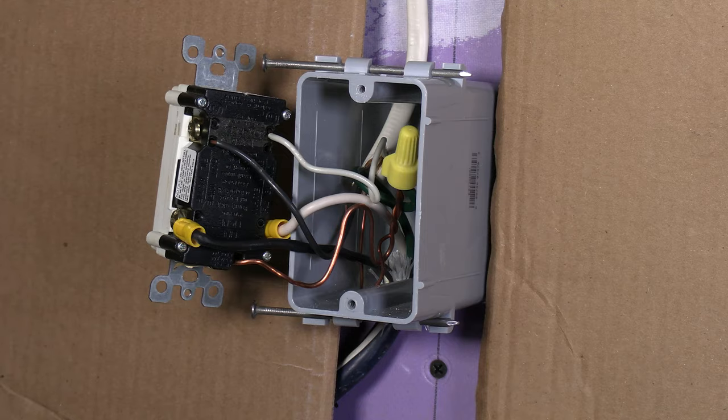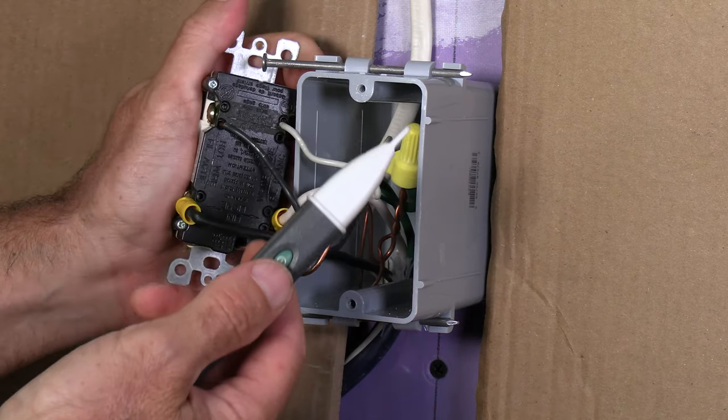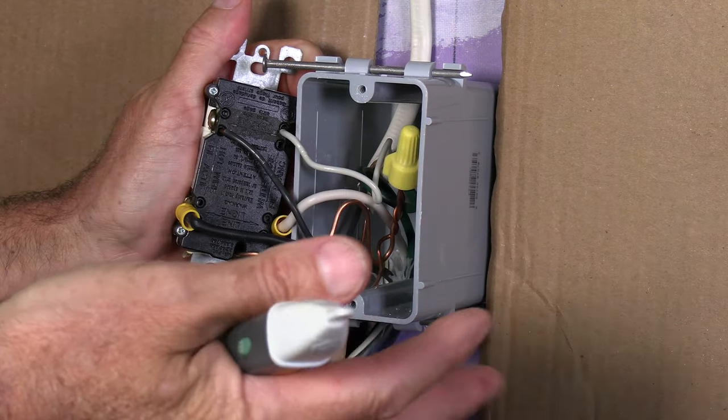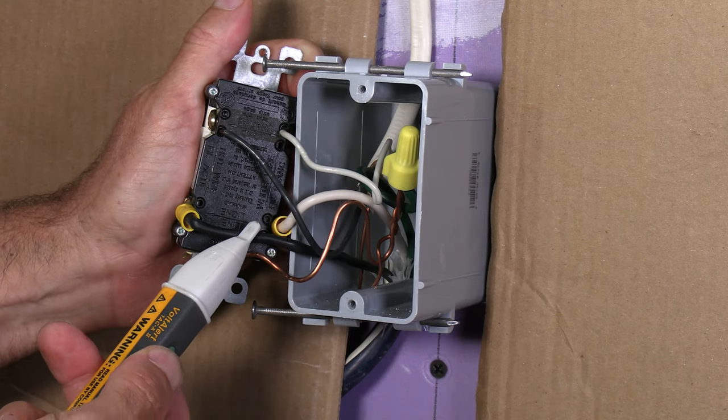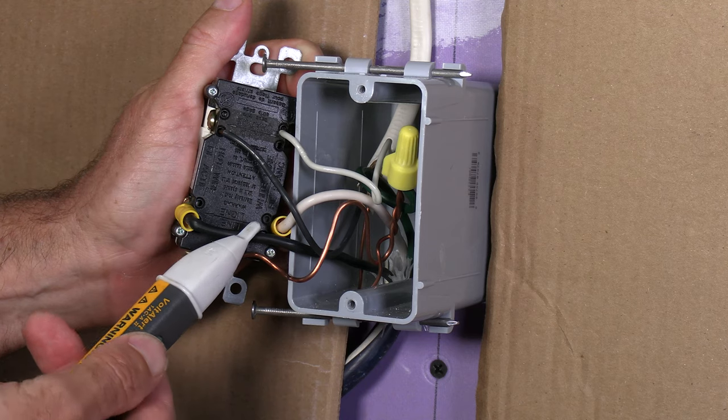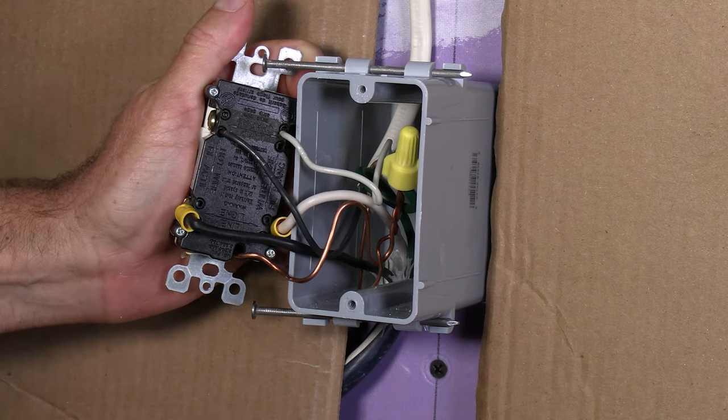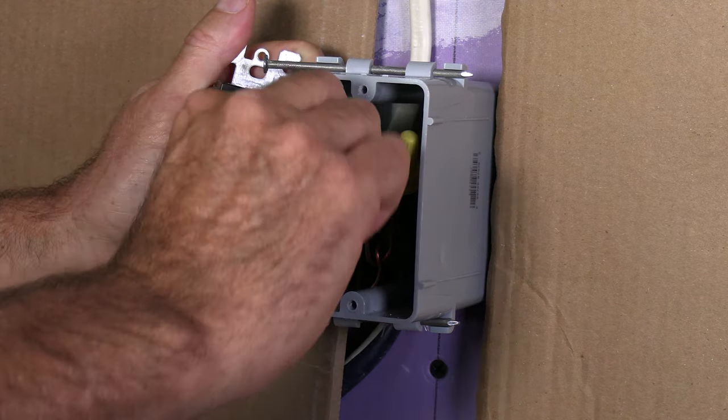Just the only thing you really need to know is the line coming into the GFI is where your power is and you want to use your voltage sensor. If you're not sure when you take everything apart and you forgot which one goes to which, you can use your voltage sensor to kind of hold it on there and it'll light up for you and show you which one is your line. Okay. And then hook the load to your downstream plugs.